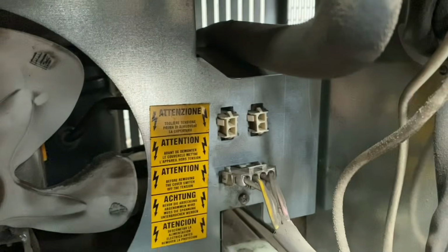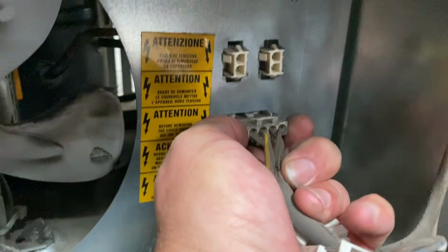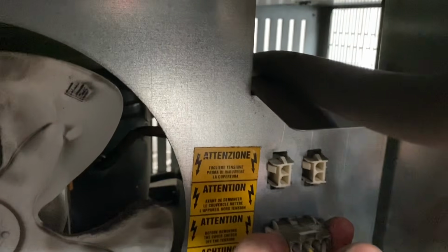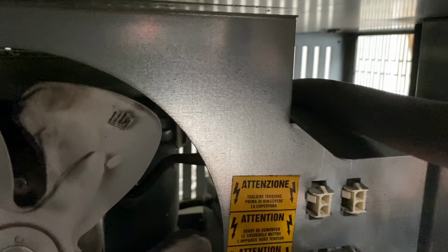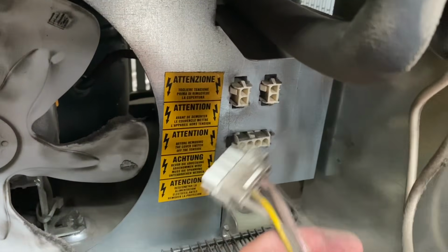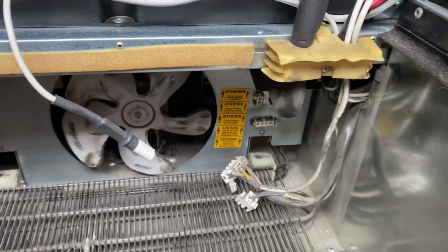So if you look at the wiring, there's 3 connections. 2 top connections are for the back fans, and the bottom connection is the actual power to the chiller unit. So if we take those 3 off, and then start to pull the chiller out.